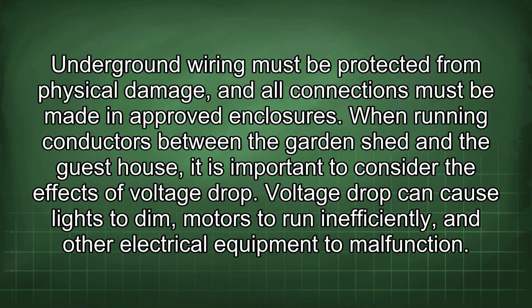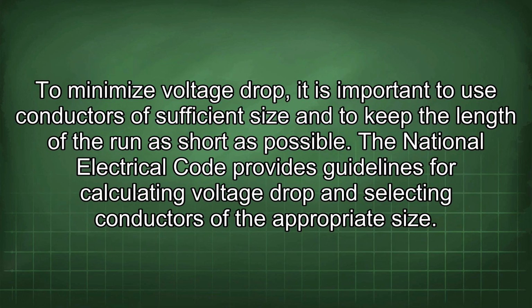When running conductors between the garden shed and the guest house, it is important to consider the effects of voltage drop. Voltage drop can cause lights to dim, motors to run inefficiently, and other electrical equipment to malfunction. To minimize voltage drop, it is important to use conductors of sufficient size and to keep the length of the run as short as possible. The National Electrical Code provides guidelines for calculating voltage drop and selecting conductors of the appropriate size.